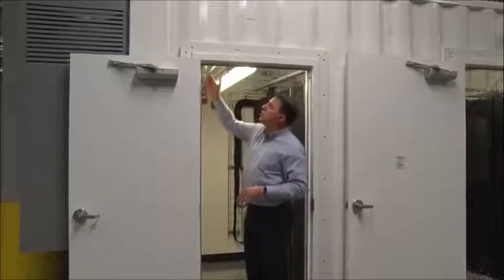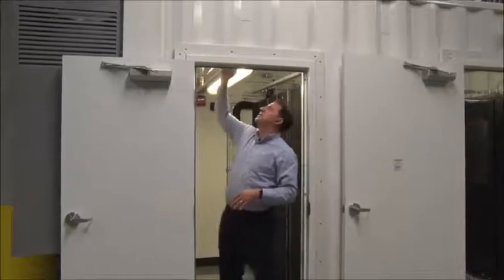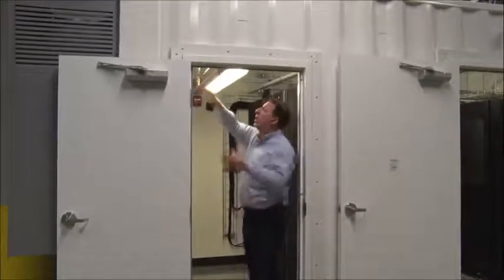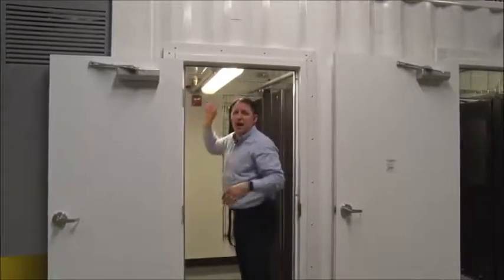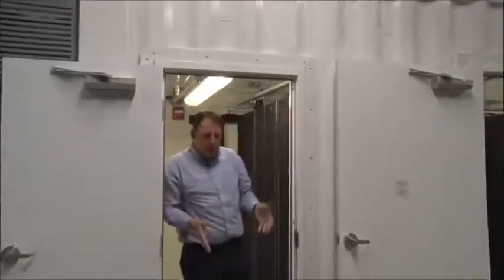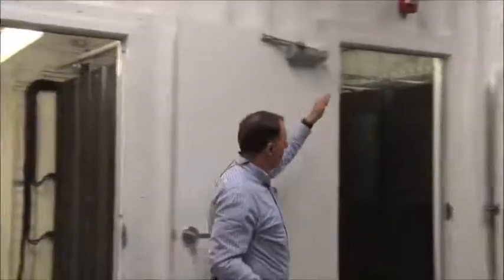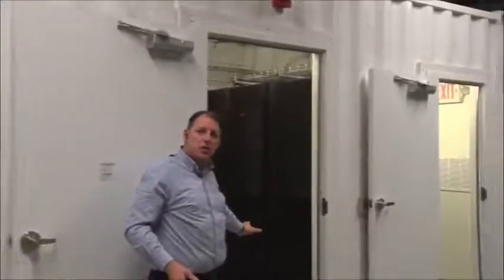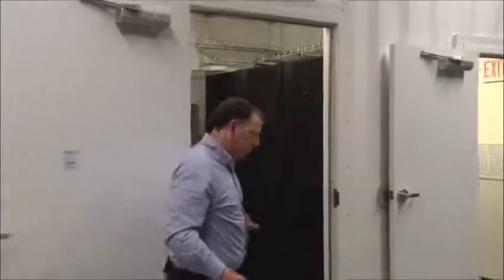The cold air blows in from the top. I've got this contained ceiling here where I can take the cold air across the top, and it falls into the hot aisle. Then we take it out and it comes over the top, drops down into the cold aisle. So that air comes down into the cold aisle, goes through the front of the racks, into the hot aisle, and is vented out to the condensers on the side.